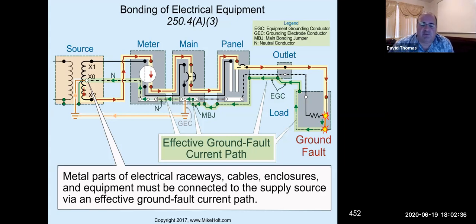So if everything's been designed properly, then my breaker protects the wires, and if that breaker trips, my wires will not melt down, causing further damage to the building. So the idea is also that the wires can be reused. They're not like a fusible link. They're not meant to work one time only.